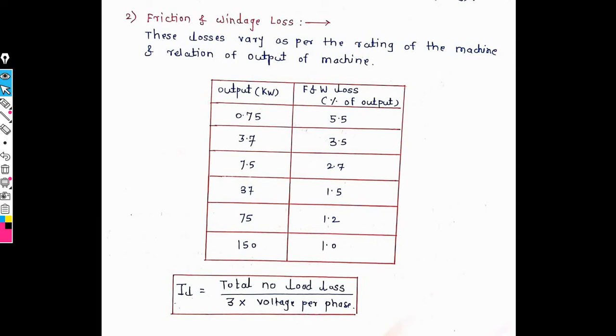In magnetizing current, we first find out the loss current Il, which equals total no-load losses divided by (3 × voltage per phase). No-load current I₀ equals the square root of Im² plus IL². Calculation of magnetizing current and core loss component is very important in three-phase induction motor with respect to stator and rotor core. We calculate total magnetizing MMF, obtain the value of IL, find core loss component, and the three parameters — IR loss, friction loss, and windage loss — depend on output in kilowatt.